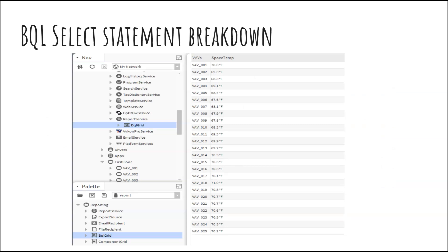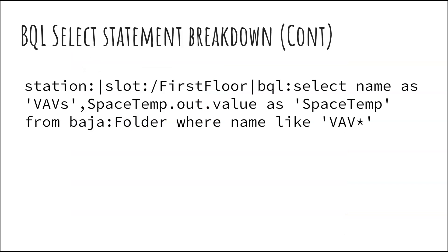So after I put in a specific statement, let's look at a breakdown. With this BQL query, I wanted to look for my VAVs and put the space temp next to them in a grid. So I typed in station:slot for the first floor — I hit Control+L and then created a BQL select to show the VAVs and the space temp value.